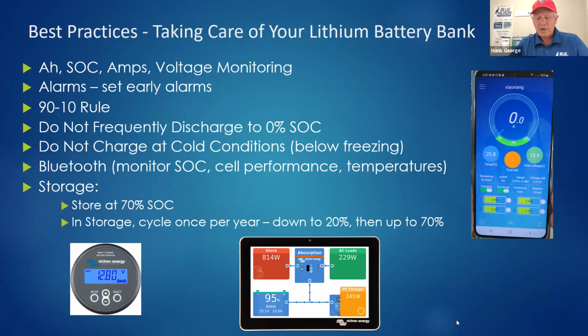But then over time, it starts to drift. And it's not a drift in the device itself. It's the way it has to approximate how many amps you used over some finite interval. And it keeps adding all those up. But it's having to approximate that because your amps may cycle up or down within that interval. And so it's picking maybe the average of the start and end point, but who knows, maybe you had a spike or a big dip somewhere between those points. So the thing to take away from this is, don't hang your head on state of charge and say, oh, it says I'm at 50%. Well, it might be, but if it's been a long time since you've done a full charge all the way up to float, it could be off. And that's how you calibrate these devices. And even in our BMS, that's how you calibrate it as well. It self-calibrates if you charge all the way up to float.